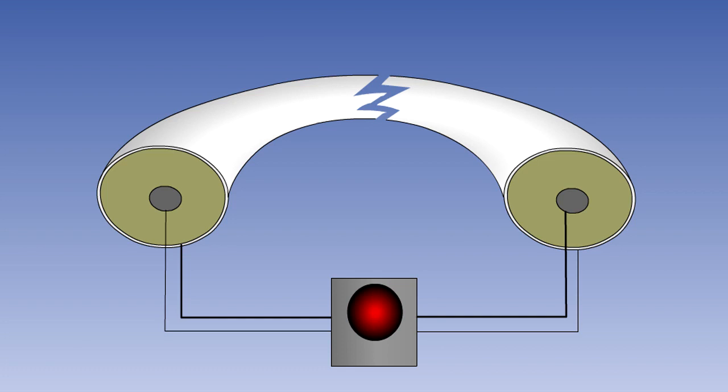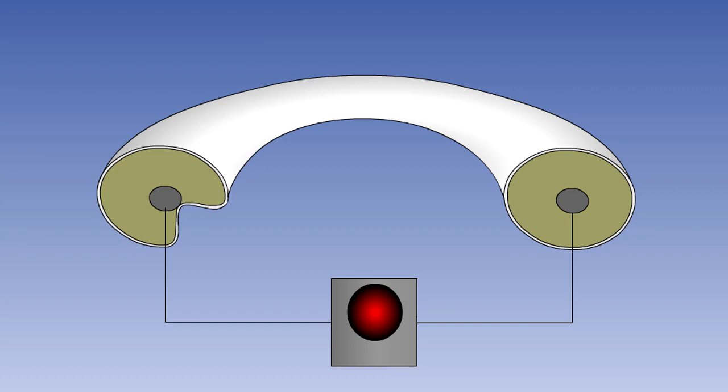Resistance and capacitive firewire systems have the detector connected at both ends. So with a single break, the detector will continue to function. The system test checks the continuity of the loop as well as the warning system, so if there is a break, the test will fail. If a resistive firewire is short-circuited, it will give a fire warning.